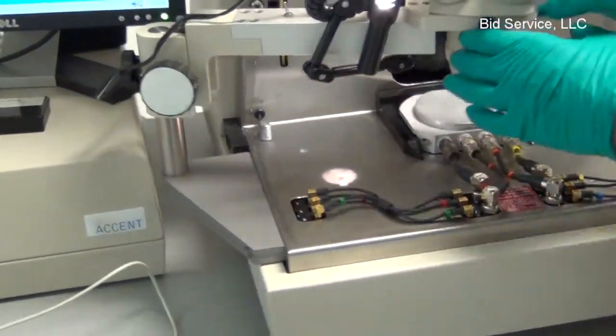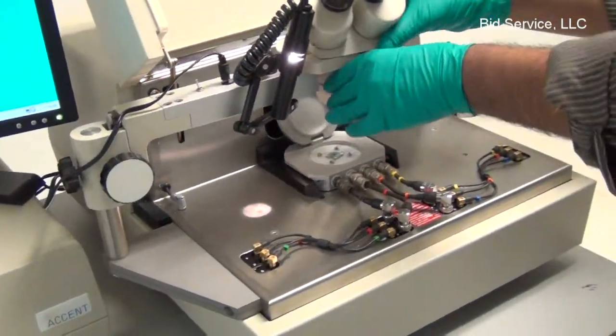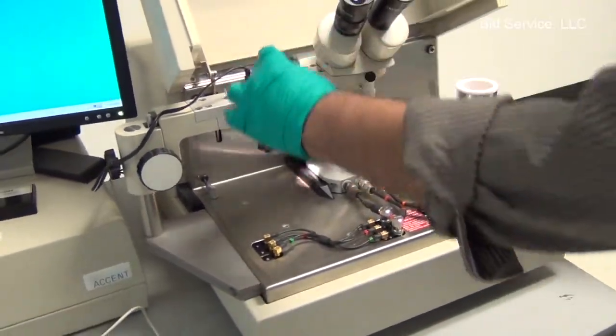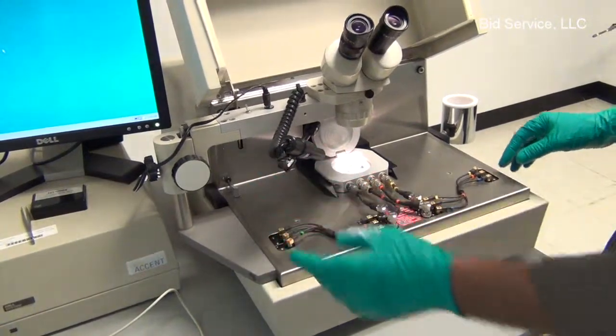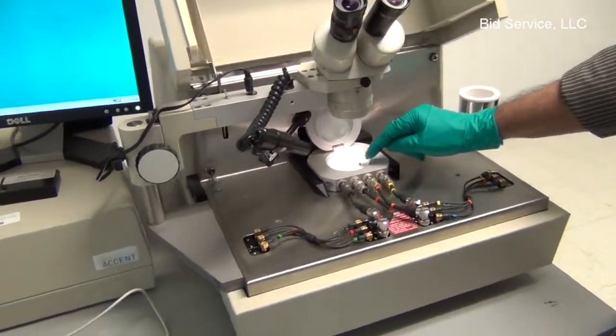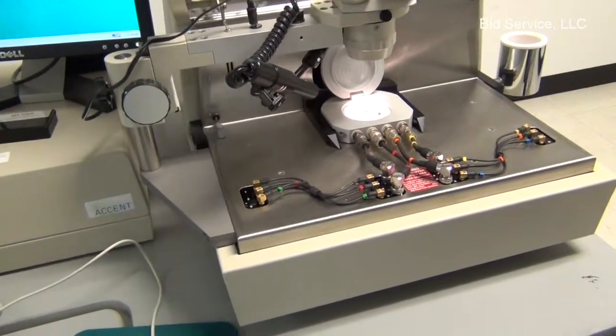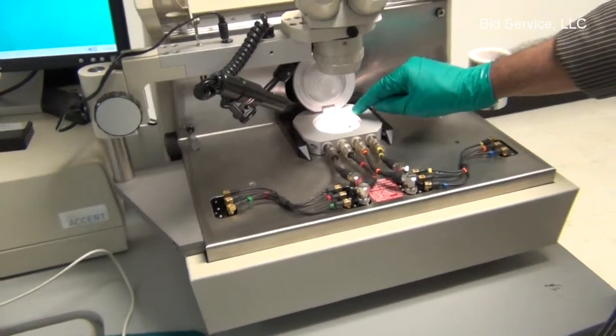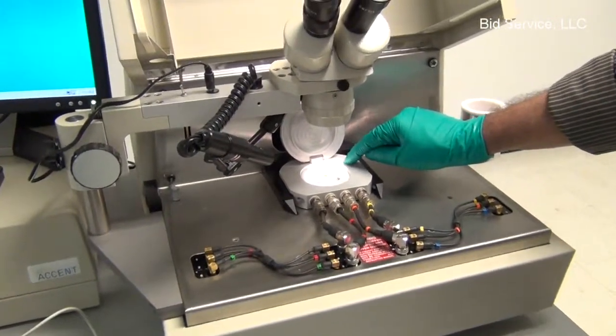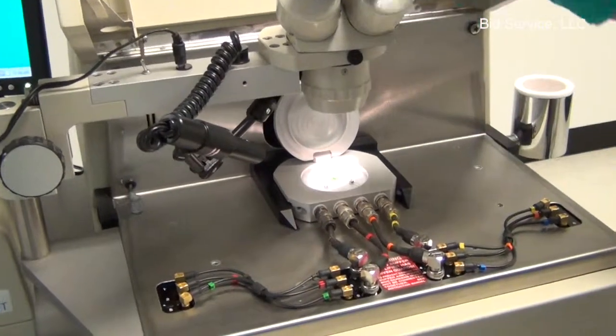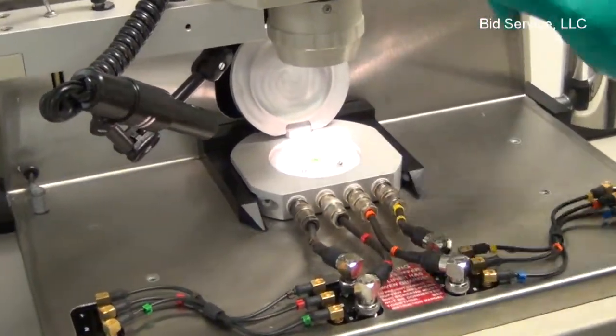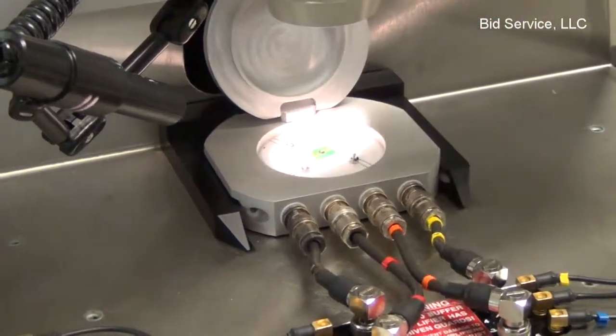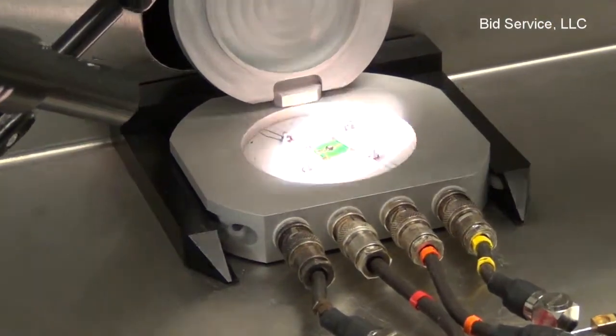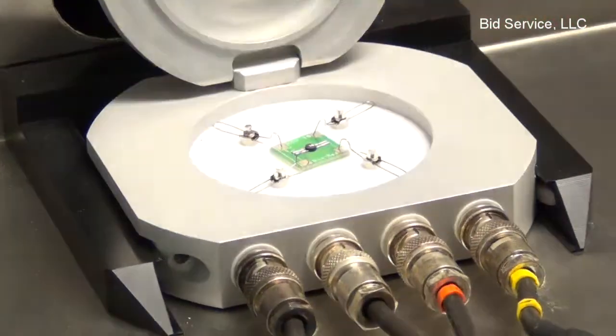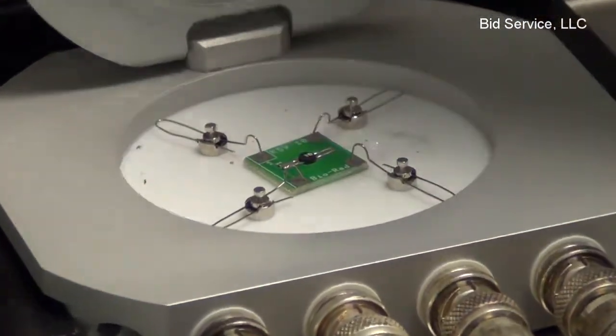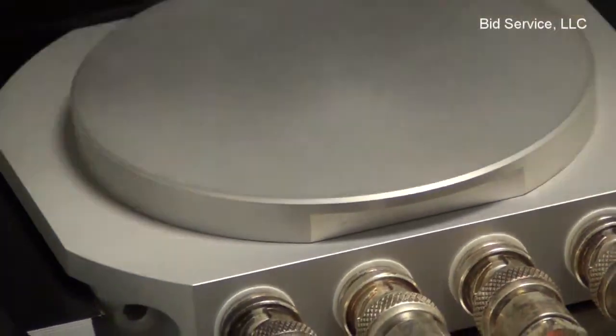There is a microscope in order to view the sample surface and adjust the probe pins. We have to make sure that the probe pins are not touching the metallic wall here. In order to start the measurement, make sure you close the lid and close the door.